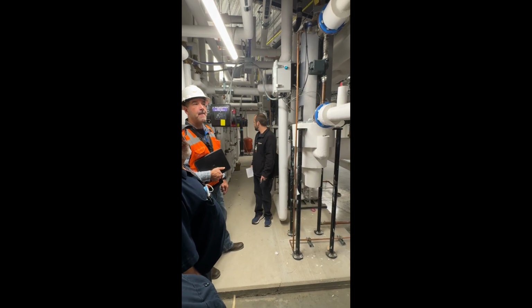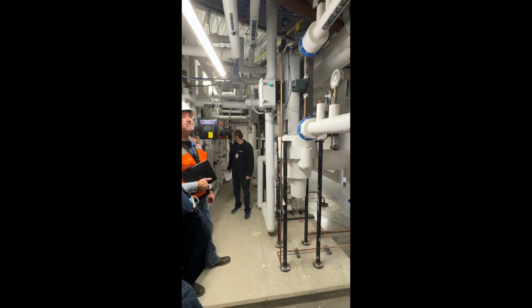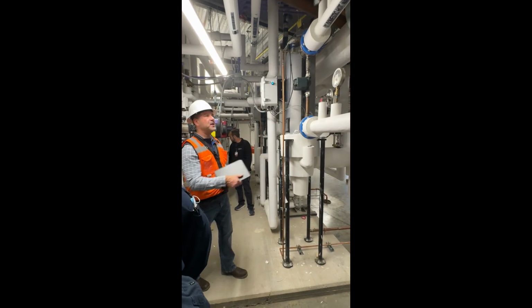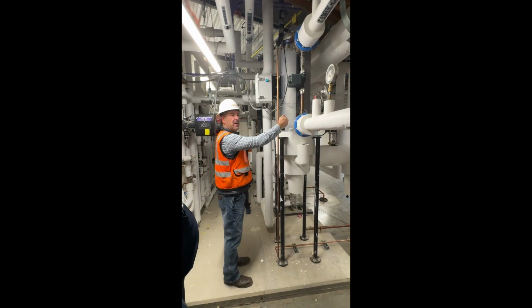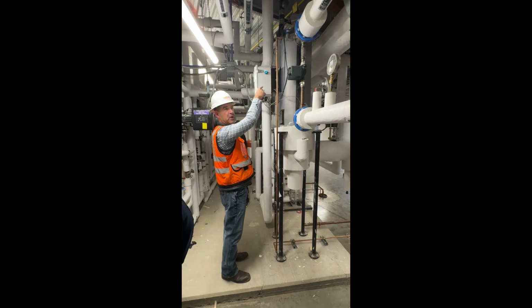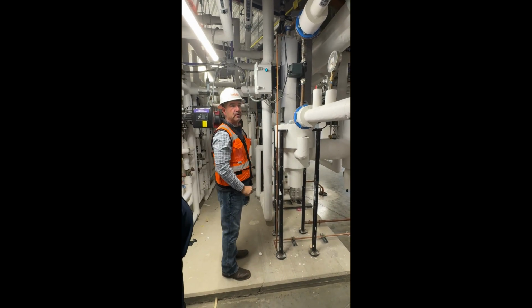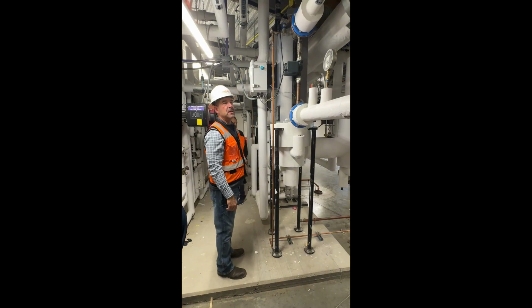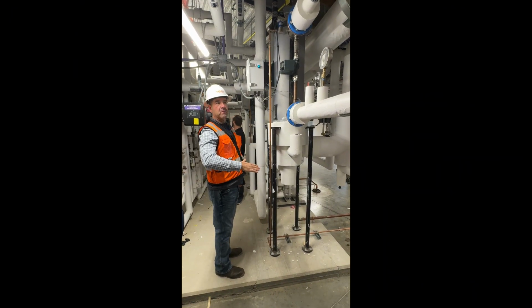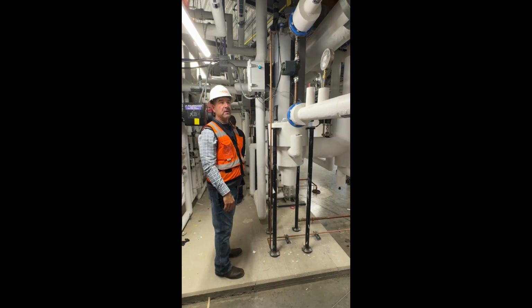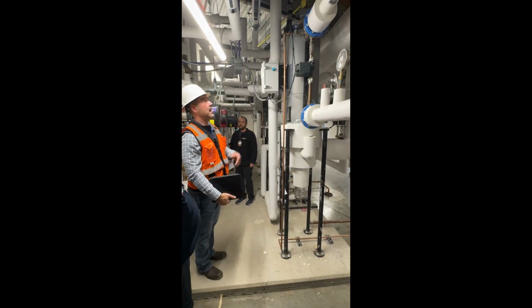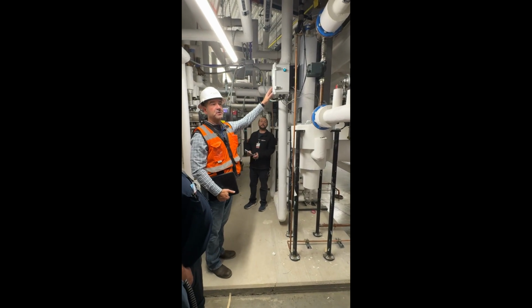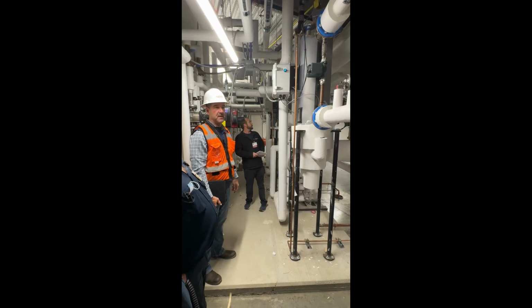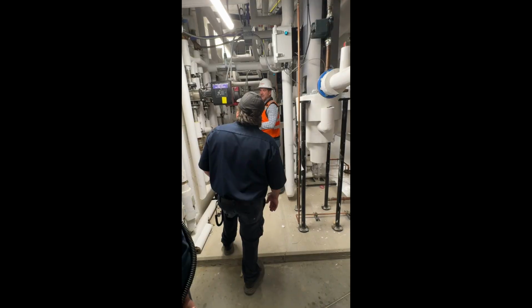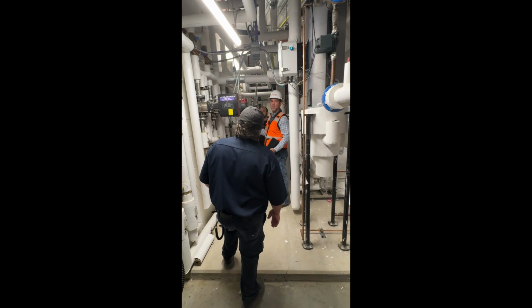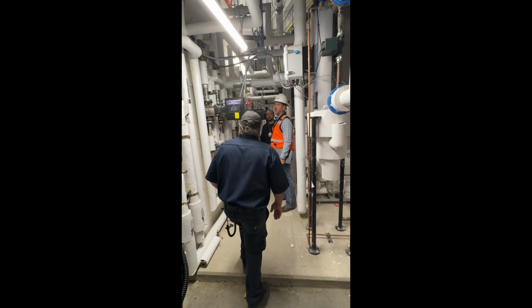So is there any issues that occur if that circulator pump goes out? Not really. All that does is, so obviously you got water coming in. You want to make sure you get good stratification on that water. That's all that pump is doing. So you may just have a colder water temp on the inlet than the outlet, but outside of that, no. Now it will tell you that the pump circulator is bad, but it's not going to shut the system down. Good question. Mixing valves, all they're doing is blending cold water with hot water to maintain the set point.